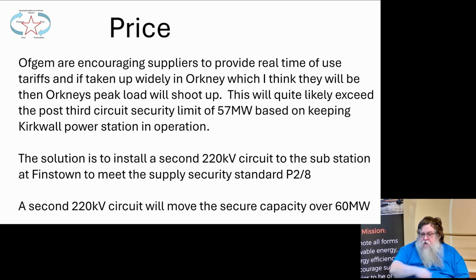Ofgem are encouraging suppliers to provide real-time use of tariffs, time of use tariffs, and if taken up widely in Orkney, which I think they will be, then Orkney's peak load will shoot up. So if at the moment you're on a tariff where you get 3 hours relatively cheap at night, 3 hours relatively cheap in the afternoon, and 3 hours relatively cheap in the evening, and you then find out that you could actually operate your system by taking 8 hours of electricity overnight at a much lower rate, you'll jump. But when you do that, what we'll find is that the overnight load in Orkney will shoot up.